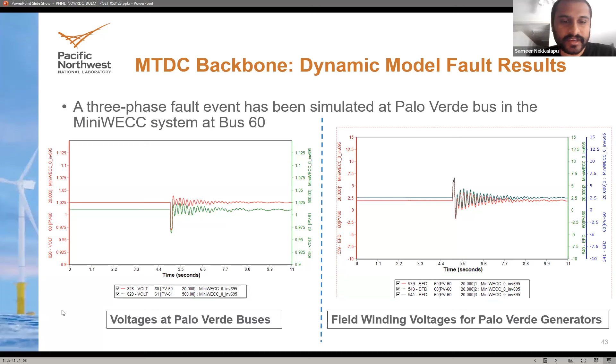Next slide, please. We also ran a frequency event by tripping a generator at Bridger, a location in Wyoming, corresponding to bus 74 in the MiniWECC system. We have a flat start until 5 seconds, and at 5 seconds we trip this generator, which is 214 megawatts, and the system does recover. But we have some issues running the model for longer time for frequency trip events due to some numerical issues we're still trying to smooth out.